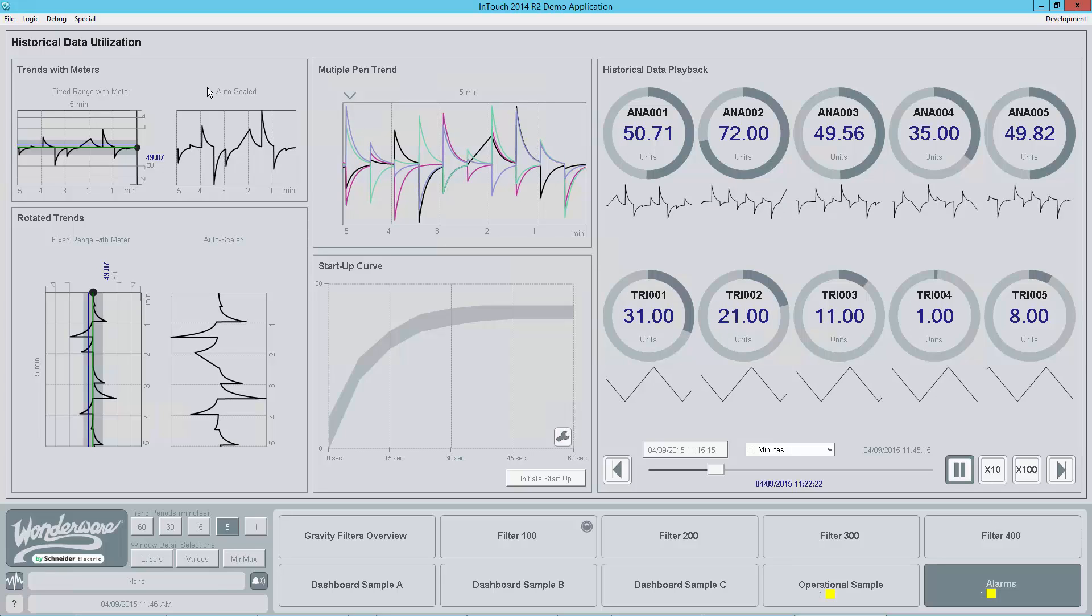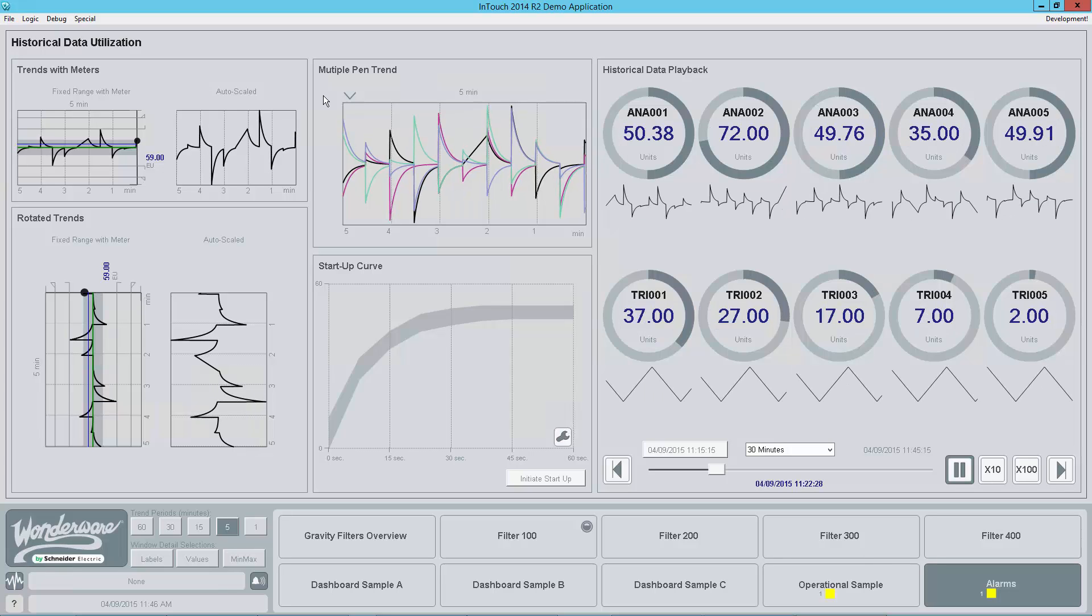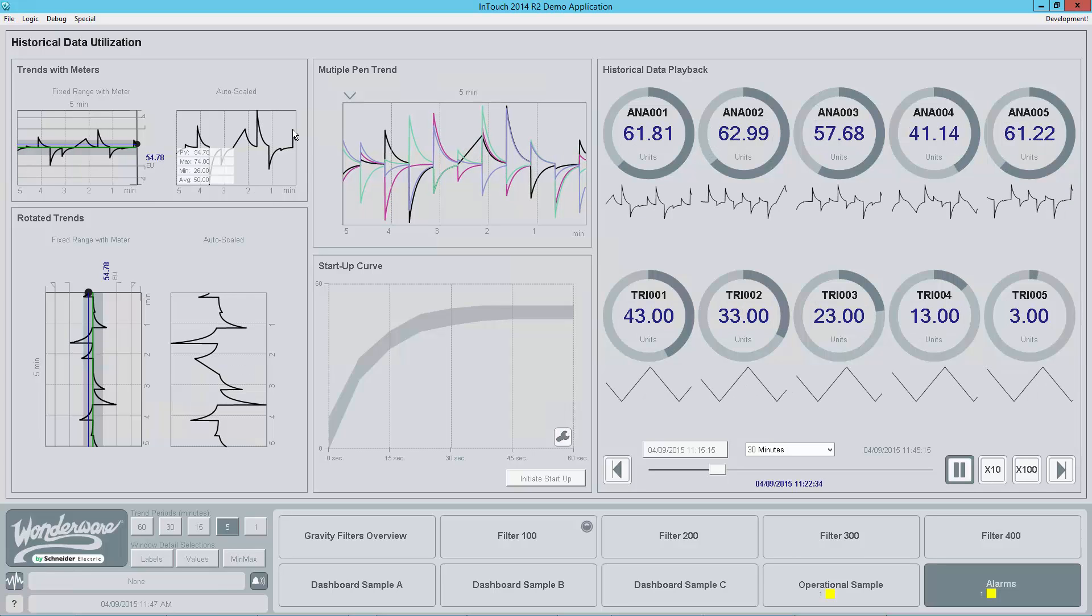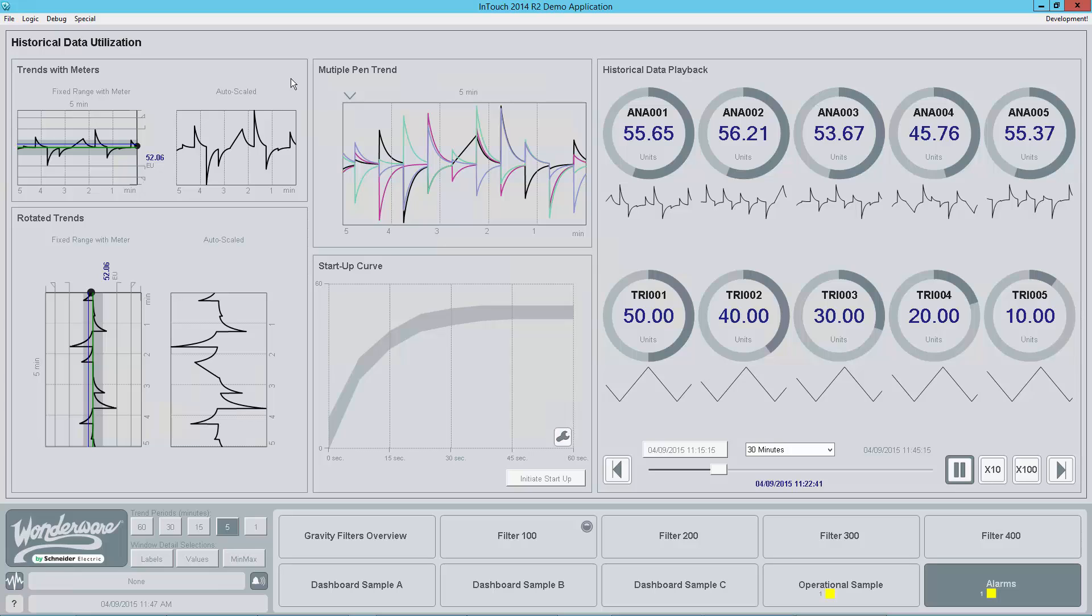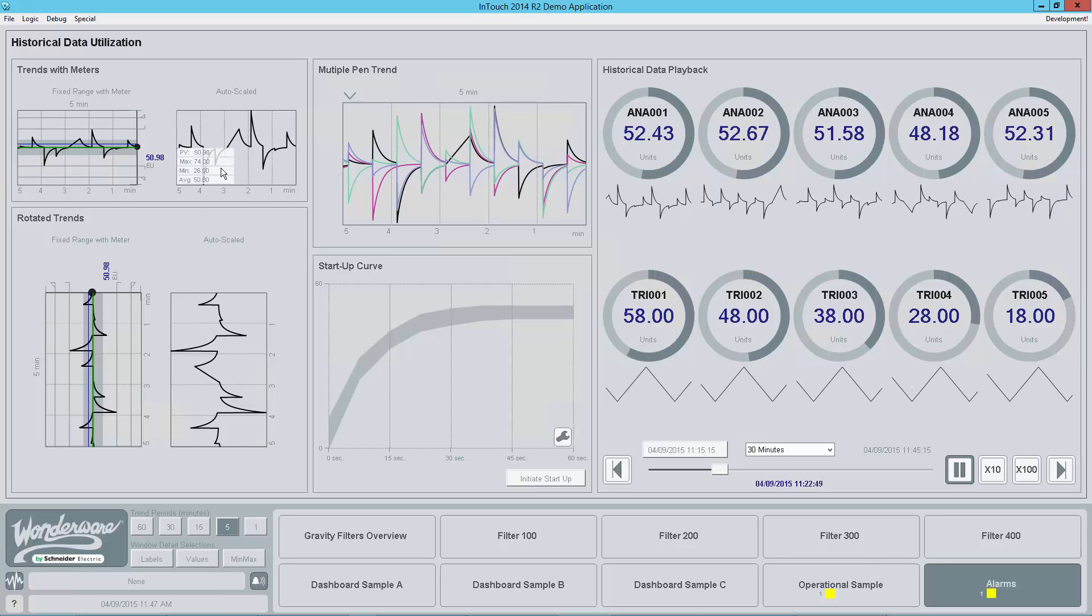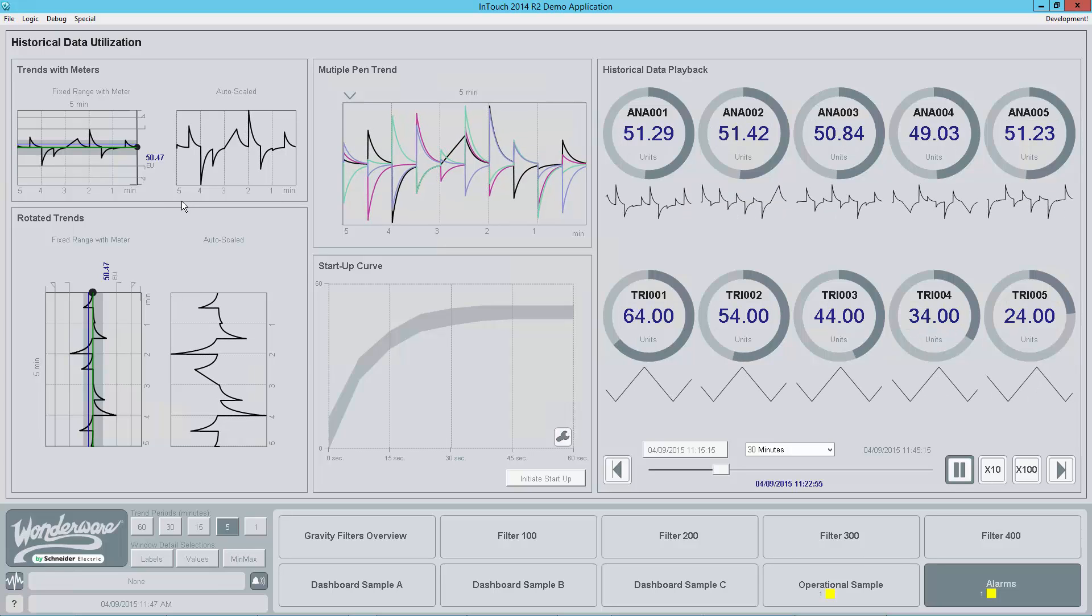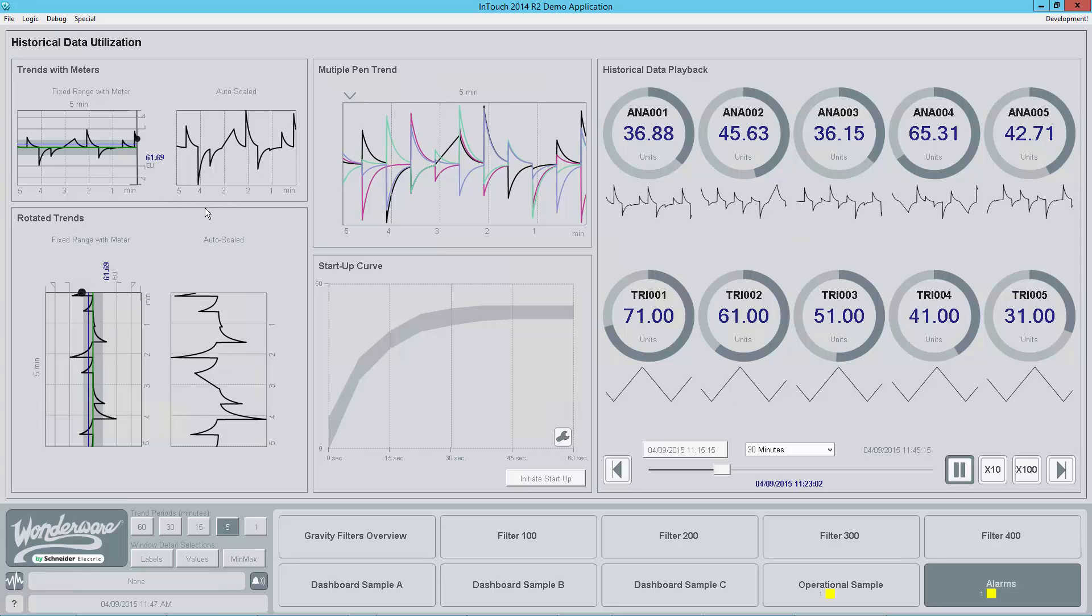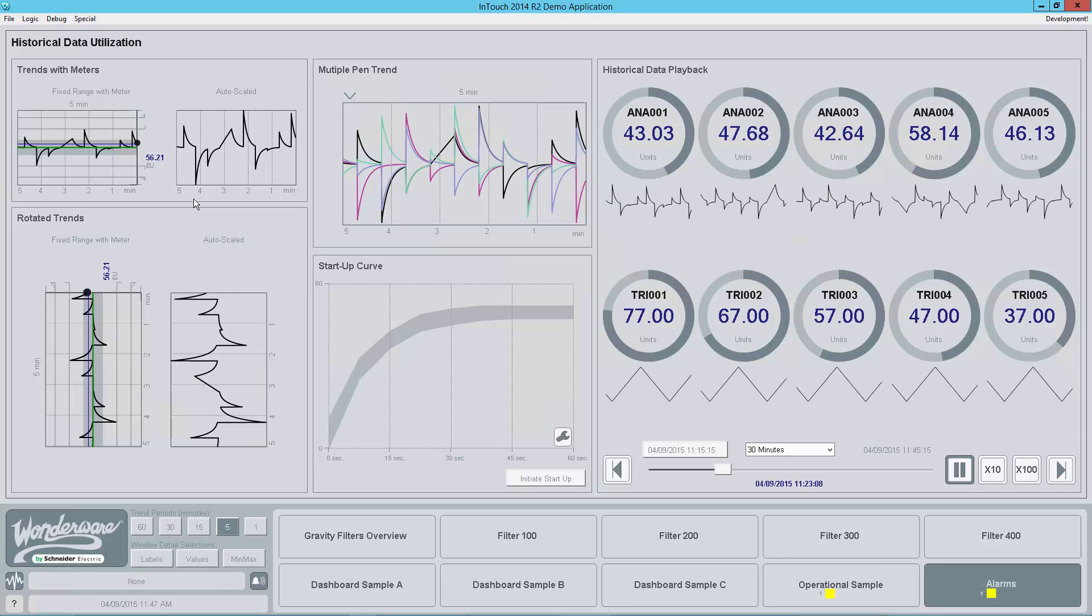This one on the right, which is labeled as auto-scaled, is actually the same wizard, but just with different wizard options enabled. You'll see that the meter has been turned off on the right here. Many of the lines have been turned off, and we set it to auto-scale. The key difference between the one on the left and the right is it's the same source data, but the one on the left has been scaled to extents of the range of that signal, whereas this one has been scaled to the extents of the data, not the range, but the data itself. And so this is filling it. This gives you, if you wanted to have a very clear visibility of nuances in that data where it's fluctuated, auto-scaling really helps in that case here. Again, starting from the same trend wizard which are available in the library as well.